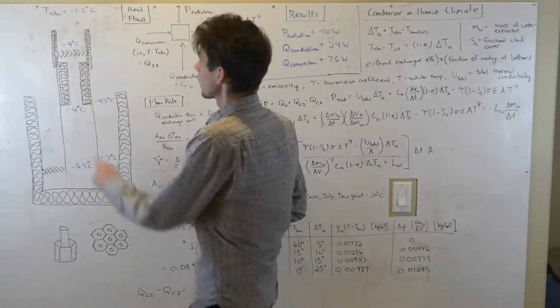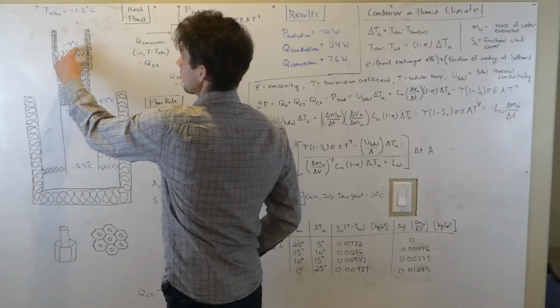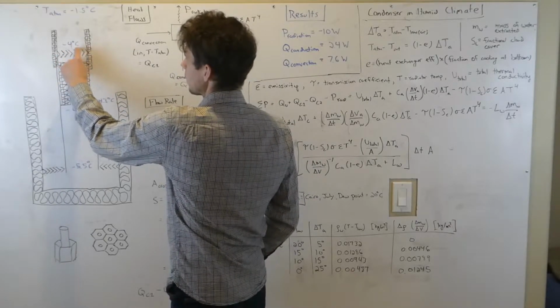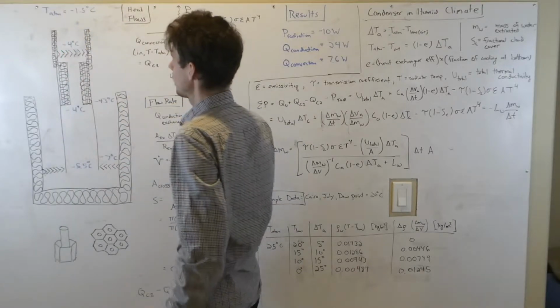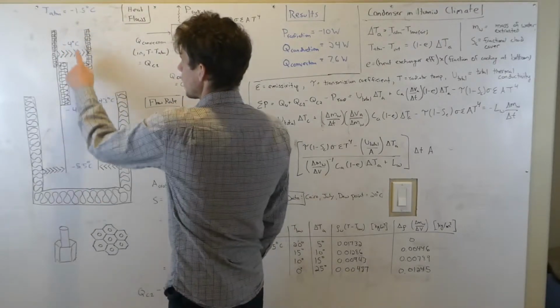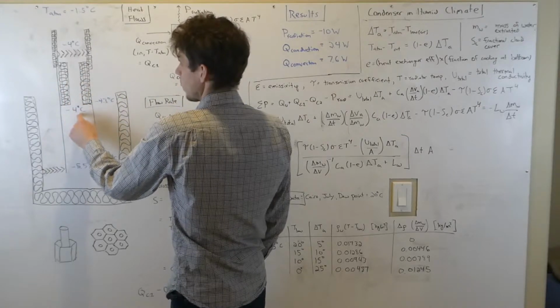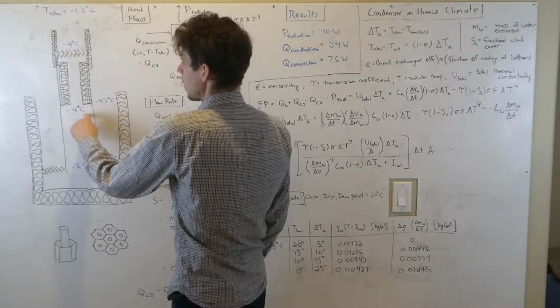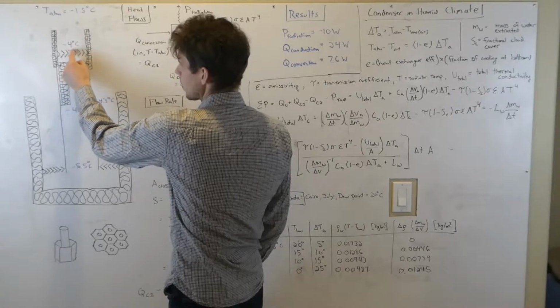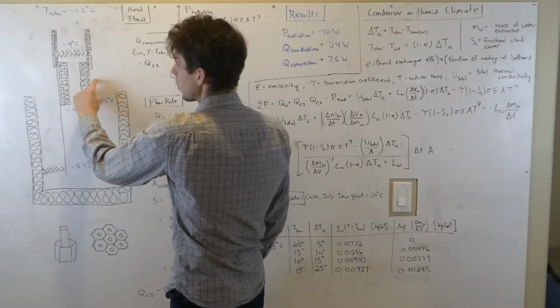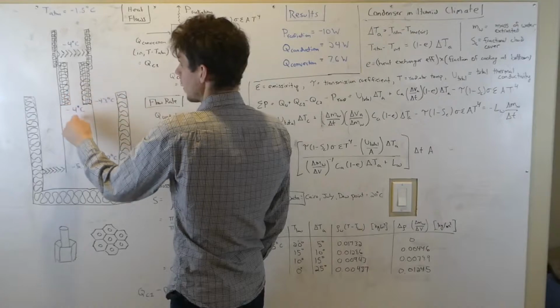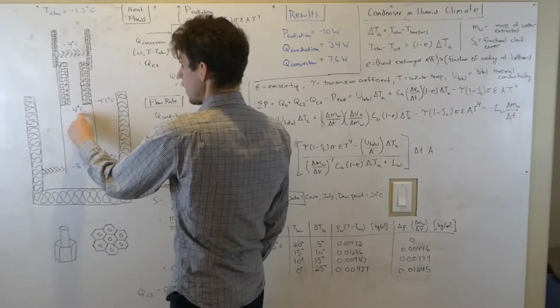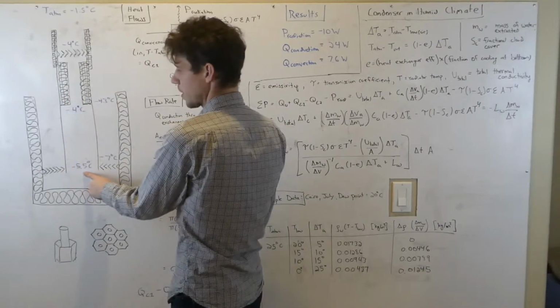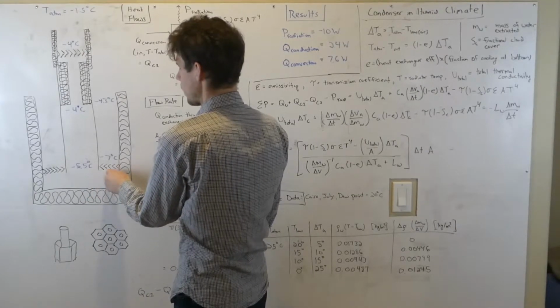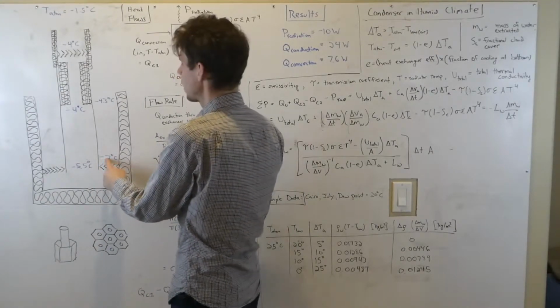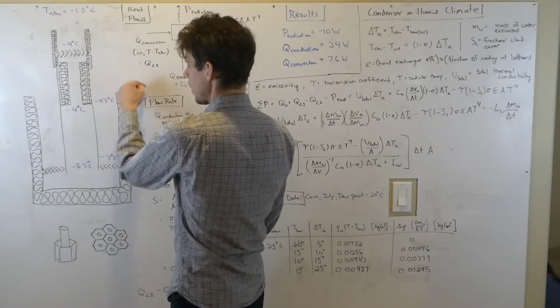Here's what we have: right above the motivator, the first radiator, the temperature has already fallen 2.5 degrees. Then it's still at 4 degrees here—it probably got a bit colder going through that first radiator, but also a bit warmer since the insulation isn't perfect, so we end up at the same temperature. Then it drops another 1.5 degrees going through the counterflow heat exchanger, another 1.5 degrees going through the second radiator, and then it warms up again on its way out of the device.